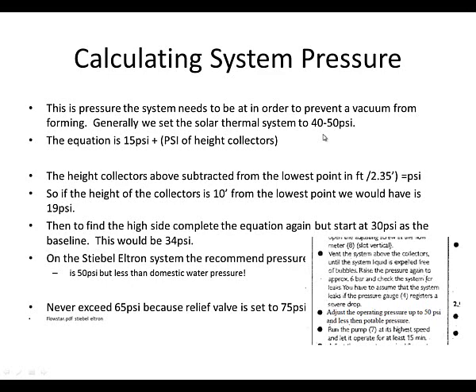It's not a static pressure we're going to see. What we need to do is calculate the height the top of the collectors are and subtract it from the lowest point on the solar thermal system. Take that distance in feet and divide it by 2.35 feet — that gives a value in PSI. Then add that to 15 PSI (which is 14.7 PSI at sea level, rounded up). So: 15 PSI plus the height-difference PSI, added together, gives the lowest point value.